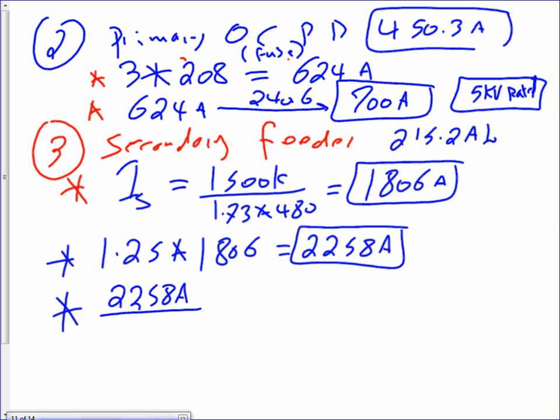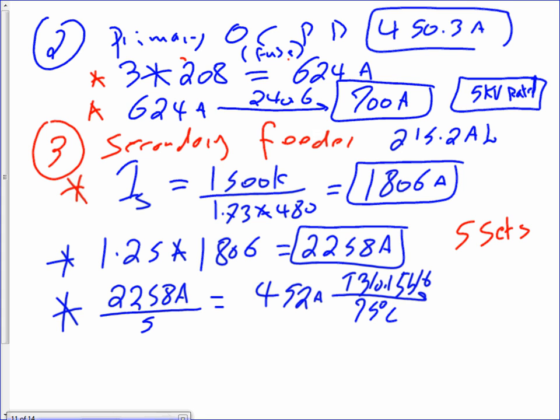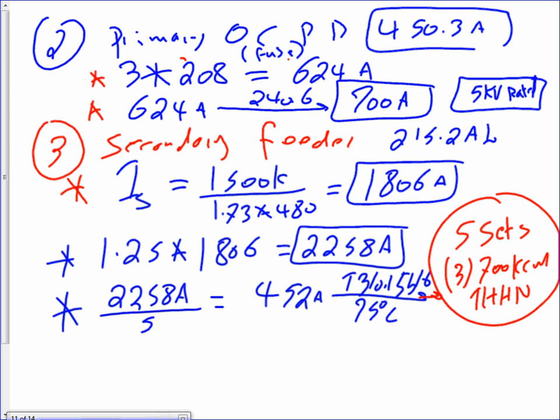2258 amps, we're going to parallel them, guys. 5 sets. If you do 5 sets, that'll get you 452 amps. And if you take this one to table 310.15 B16, under the 75-degree column, because that's low voltage, here's your conductor: 5 sets, because we're parallel, of 3 conductors. Each one of them is 700 kcm THHN. So that's the phases for this system.